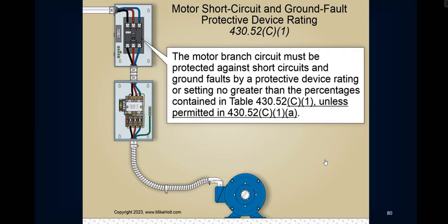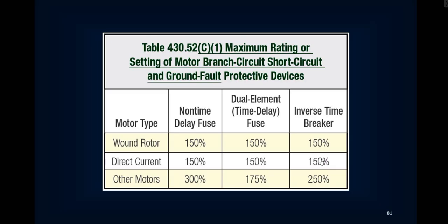So the motor branch circuit must be protected against short circuit and ground faults based on 430.52. And here's a little nugget of that table. They kind of do a condensed version of it. The non-time delay, the dual element, the inverse time breaker. We're not really on overcurrent protection right now as much as different types, but these are the types you would need to be concerned about regarding the calculation.